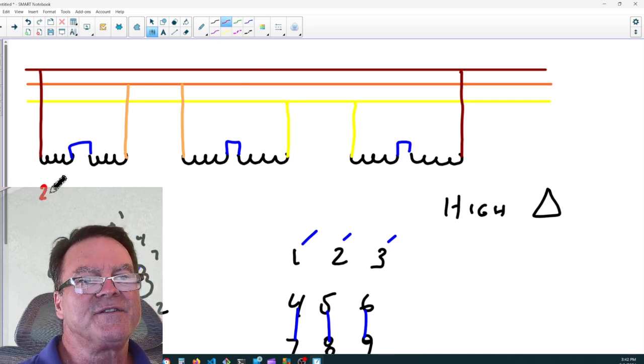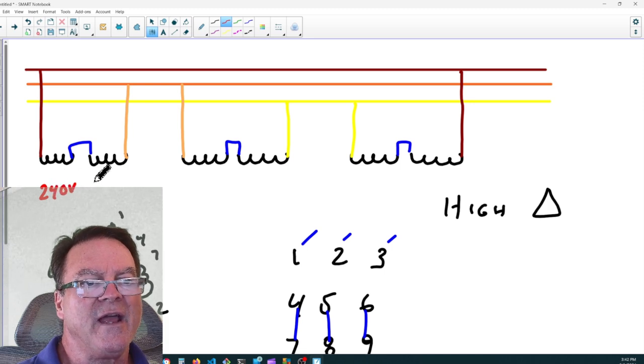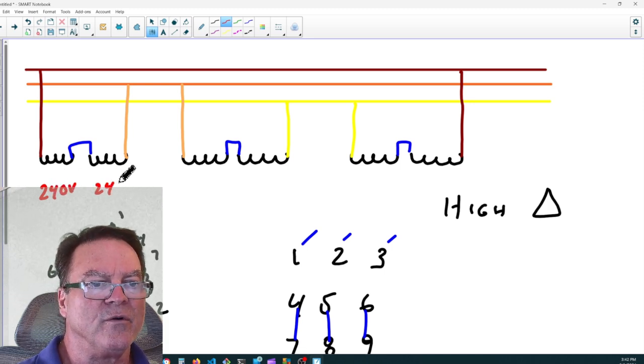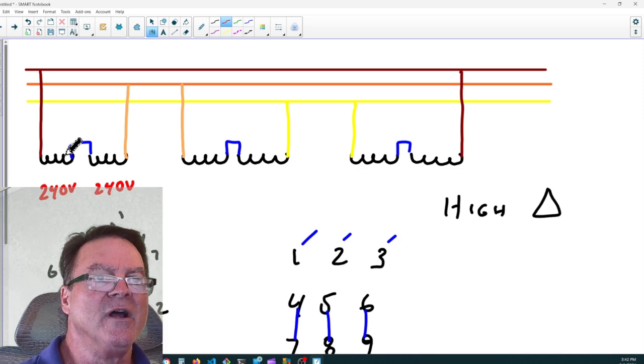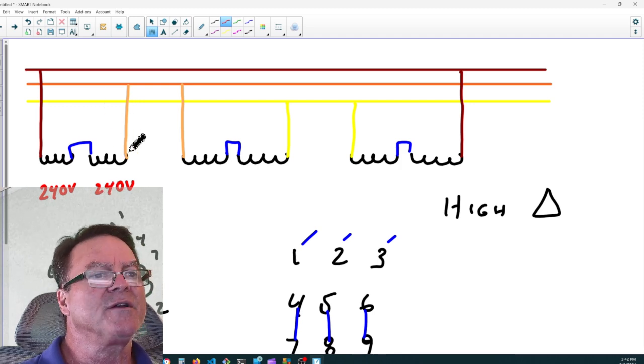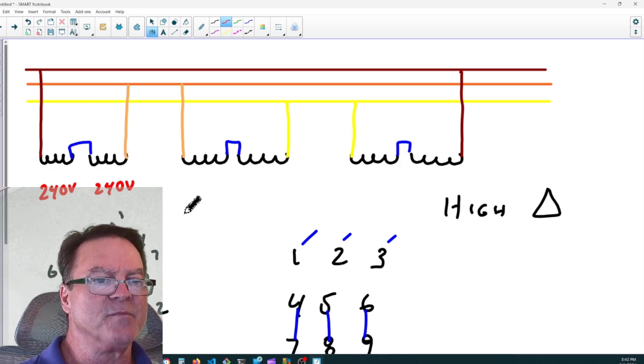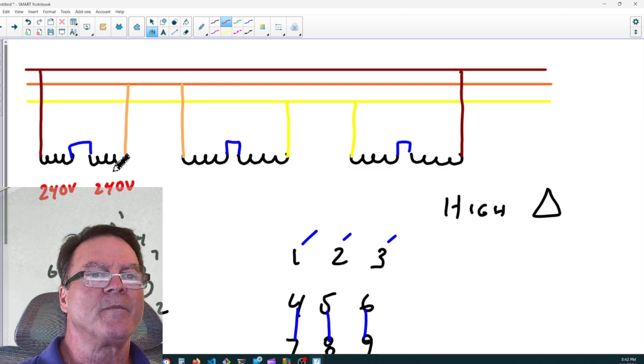Series because if this is 240 volts and this is 240 volts, when I tie the two of them together, they're good for 480 volts. So we'll put them in series, and then we can put 480 volts across them, and we can feed this motor. We won't burn it up because each coil is only seeing 240 volts.